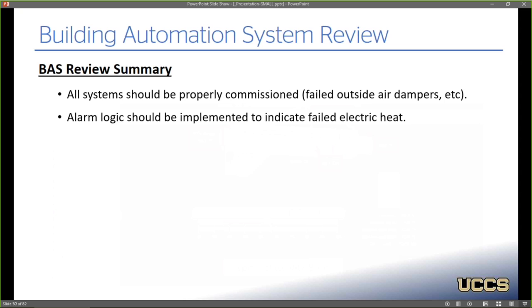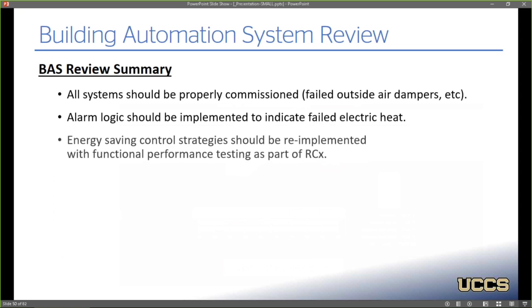They do have alarms in place for low space temperature, but because this is kind of an open office, if one heater fails, the other heaters can kind of pick up the slack a little bit, and so it's hard to identify when a specific heater has failed. And then the energy saving control strategies that are already programmed in place should be re-implemented, and maybe include some functional performance testing as part of that retro-commissioning effort. Specifically on that static pressure reset, who knows why it was disabled in the first place? There may be a reason for that, so we have to be cognizant of that fact.